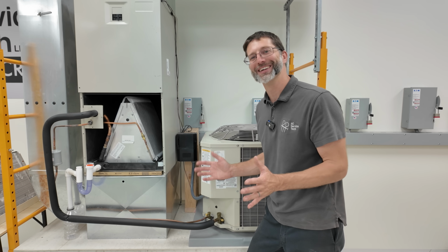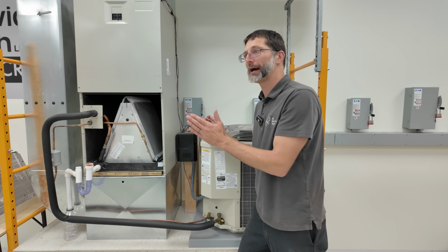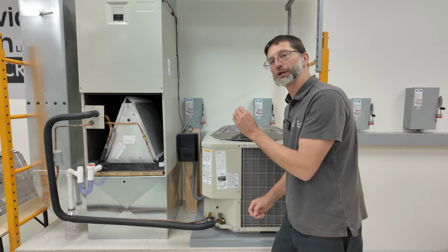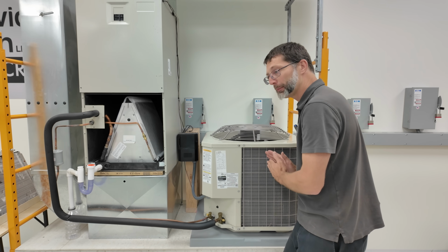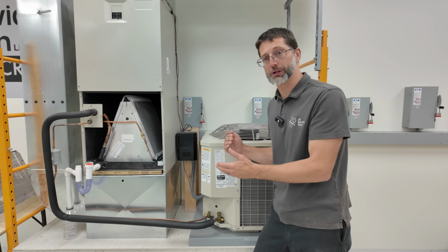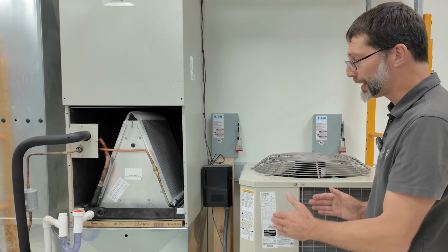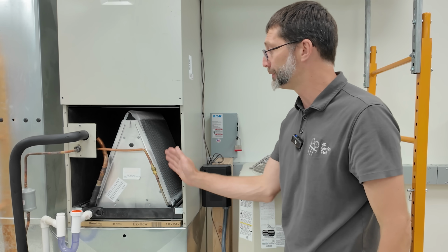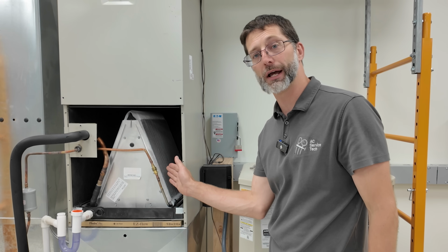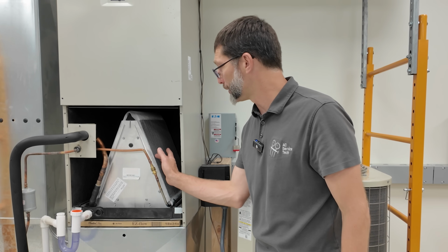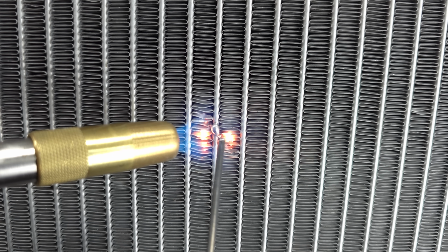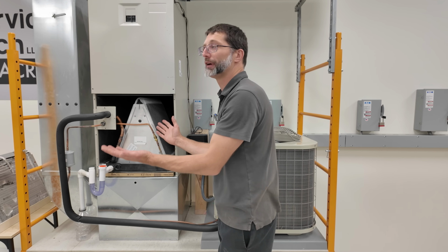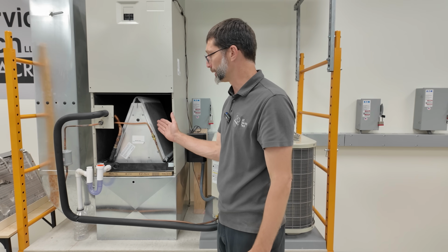The issue is, as you're seeing these little tiny pathways, there's not much aluminum there as far as the high pressure, and also if there's corrosion, that's going to be an issue. But if you do have a leak with a microchannel coil, you can fix it. After you recover the refrigerant out, you can use an aluminum soldering rod in order to fix that leak. And if it does clog off that channel, it's not that big of a deal because there's 1,025 of them, right, in the example that we were looking at.